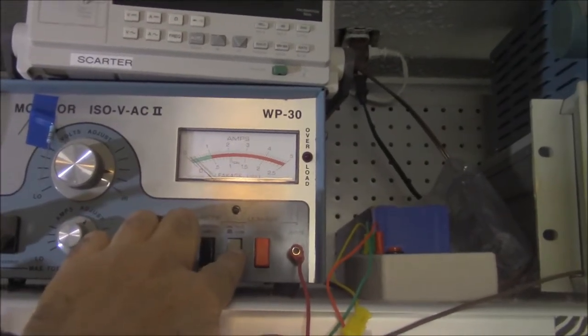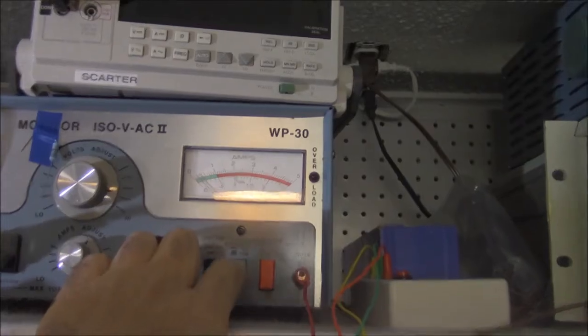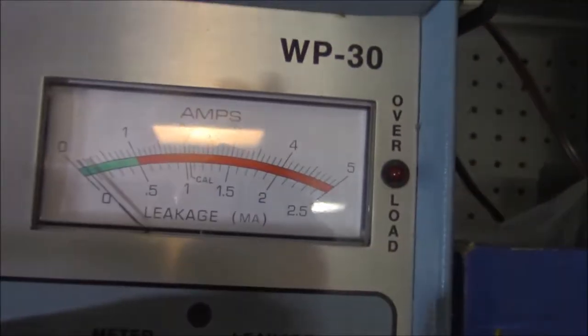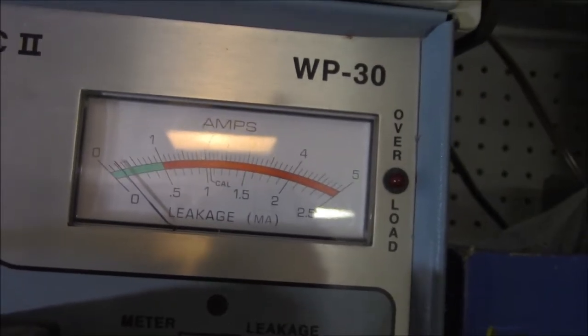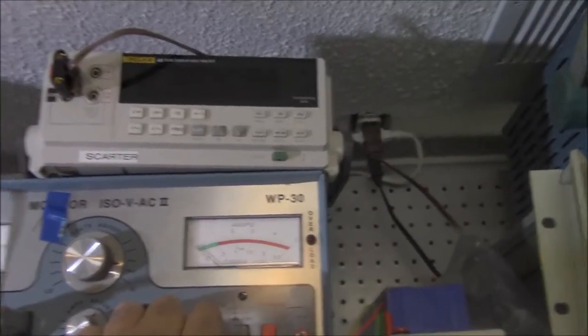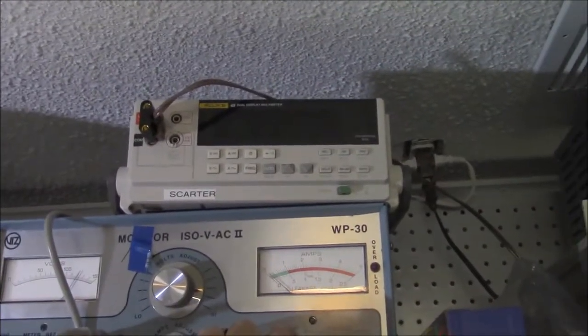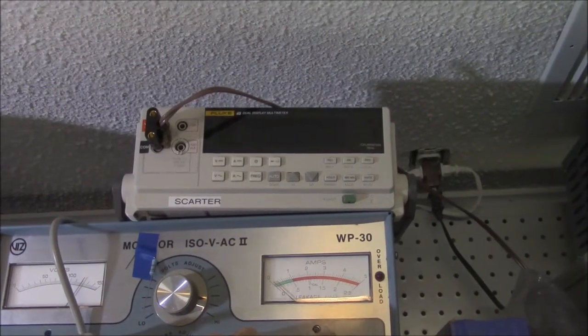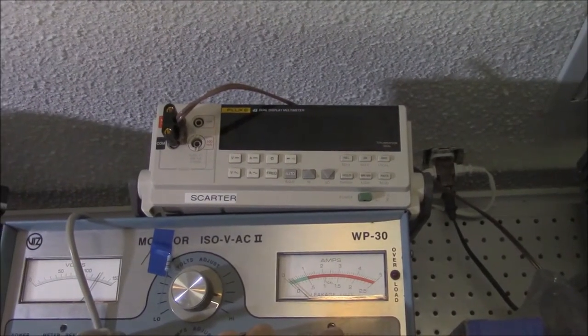Then you switch the meter into leakage mode, and it's read directly here. And then you flip this meter, basically how it's referenced back and forth. You can see at a quick glance it's within the leakage limit, which is, what is it, like half a milliamp, so 500 microamps.